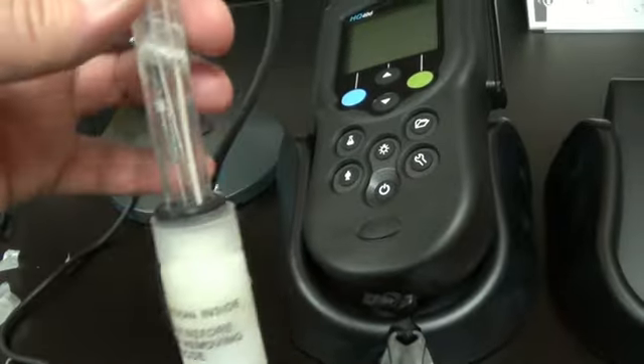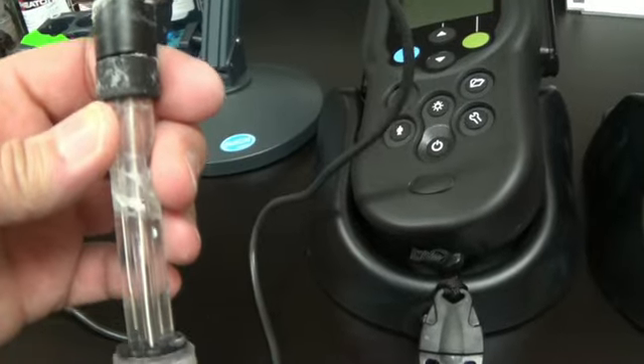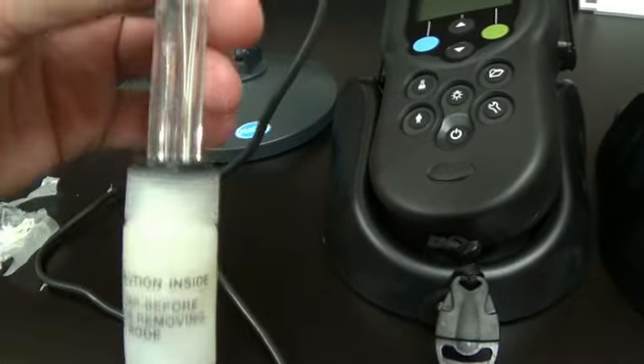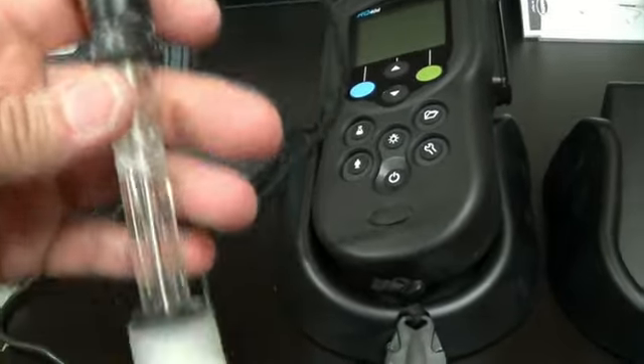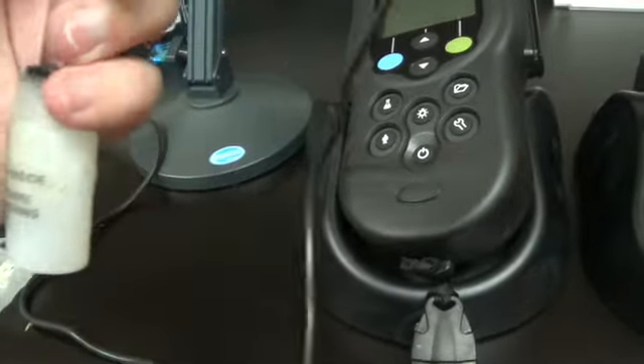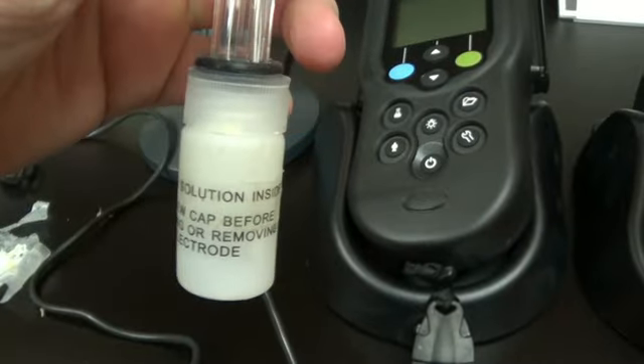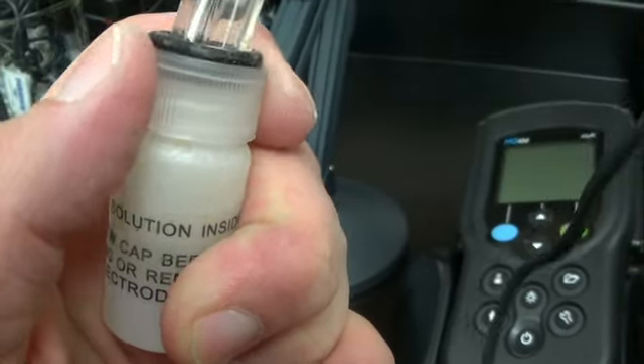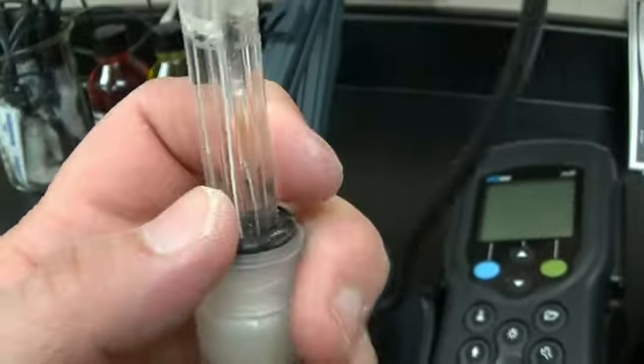So this is what the pH electrode looks like without the parafilm on it, and I had to take the cruddiest one to demonstrate. So first you want to remove this cap here, and what you do is unscrew it right there. It takes less pressure at pulling this probe out. So I loosen this first, and then the probe will pull out much easier.